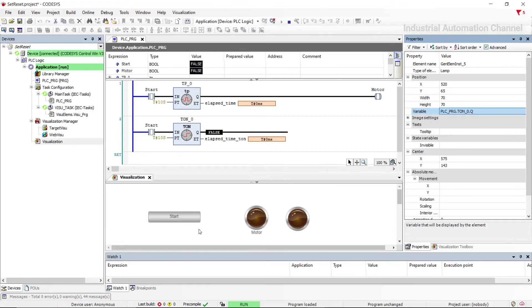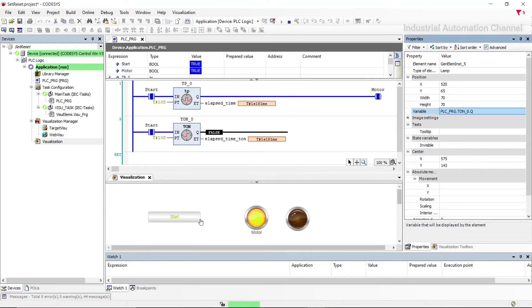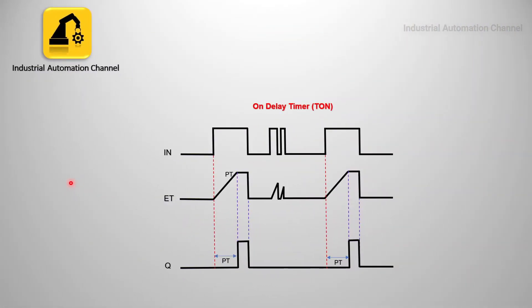So the output turns on after a delay when we change the input from false to true. But what would happen if we turn off the input before 10 seconds? As soon as we turn off the input on a TON timer, the elapsed time will be reset immediately and the output will never be activated. Here you can see the function diagram of this timer: when the input is activated, after the preset time the output will be true. If the input is turned off before the preset value, the output will remain 0.